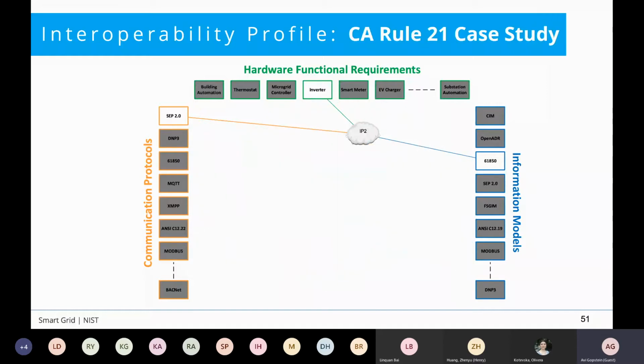Compare that to California Rule 21, which identified the inverter function, said the communication protocol had to be SEP 2.0, and the information model had to be IEC 61850. The result was the equivalent of a single interoperability profile that led to the creation of a testing and certification standard and program under UL 1741 SA. It's pretty simple: when you work with industry and reduce the implementation optionality, you can achieve interoperability.